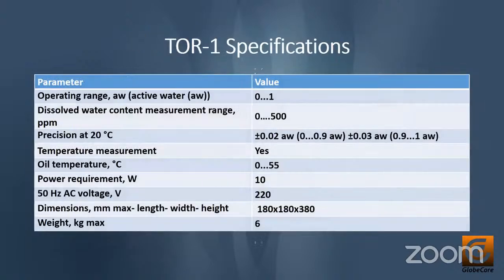The device measures such parameters as water activity, temperature, and calculates absolute water content in ppm. You can see the technical specification of the device in this table.